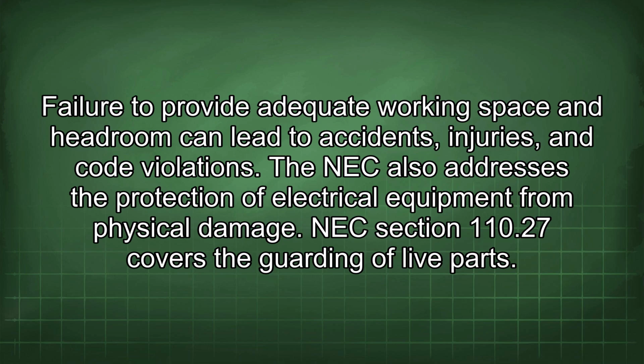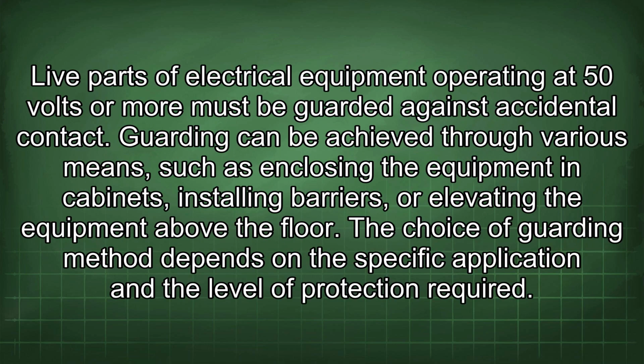The NEC also addresses the protection of electrical equipment from physical damage. NEC Section 110.27 covers the guarding of live parts. Live parts of electrical equipment operating at 50 volts or more must be guarded against accidental contact. Guarding can be achieved through various means, such as enclosing the equipment in cabinets, installing barriers, or elevating the equipment above the floor.